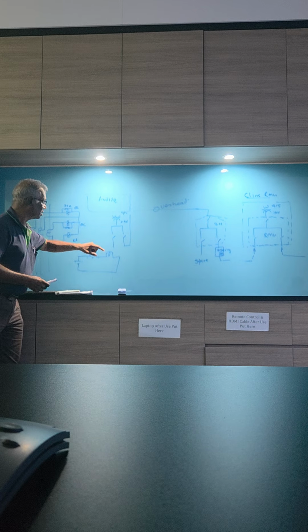Anything exceeding, that means during overload, this one will snap. We don't call it blow. Blow means it's for cable, copper cable. This is like lead. Slowly it melts and gives way. When it gives way, the voltage will try to pass into this actuator coil. So it magnetizes. You have a plunger, and the plunger trips the mechanism of that breaker. This breaker is outgoing. Here there is a breaker.